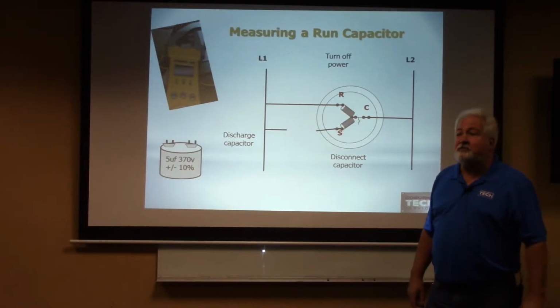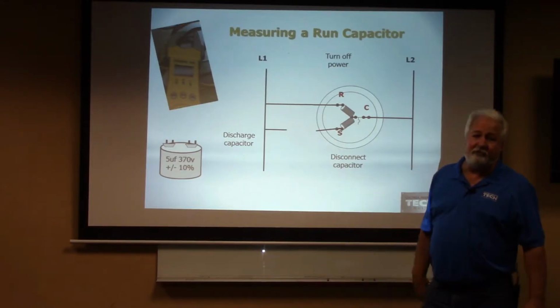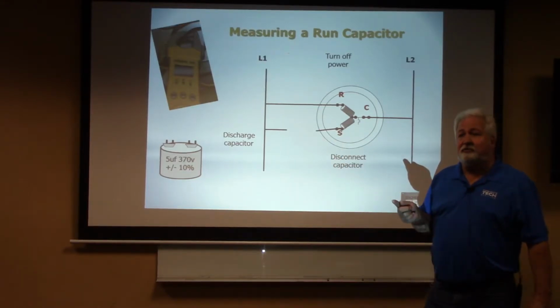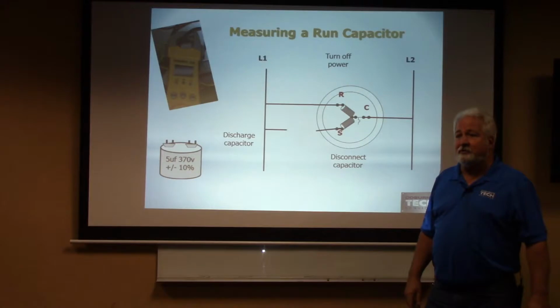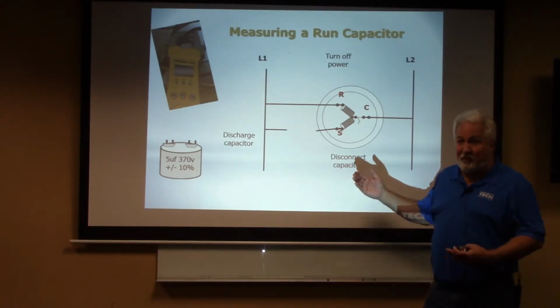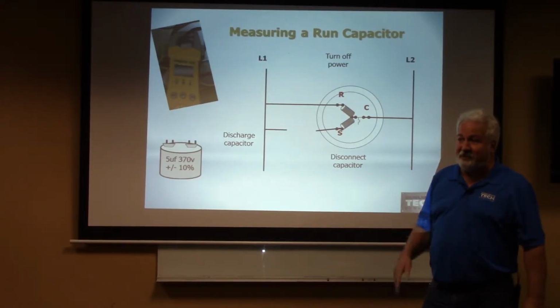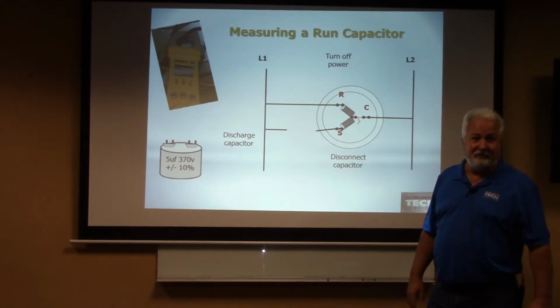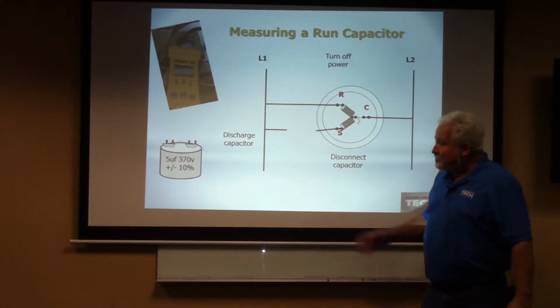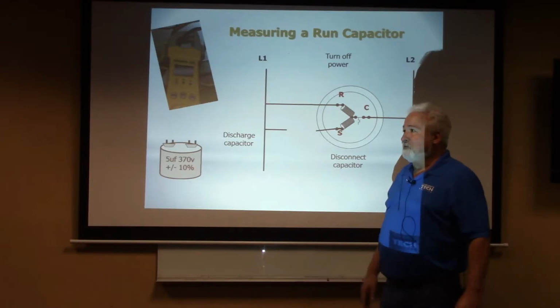We can't use screwdrivers too much anymore, because if you use screwdrivers in them, a lot of them are fused on the inside. And if I use a screwdriver across it, what happens to the amperage? Amperage goes up. If amperage goes up, the fuse may go. Is that right? So it might have been good prior to you putting the screwdriver across it, but now it's not. Does that make sense? Good. So discharge it with a 10,000 ohm resistor.